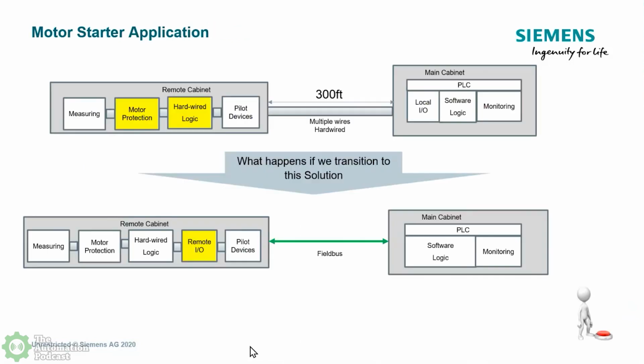So if we replace that with a field bus, and initially, back in the day for the seasoned individuals, we started working with RS 232, RS 485. For Siemens, the RS 485 communication protocol is Profibus. You may encounter Data Highway, Modbus RTU, and so forth. But the field bus started to help reduce all that wiring. It also gave some opportunity to move some things out into the remote cabinets too, because you started having bandwidth to where you could bring in multiple points of data with the same piece of wire and get statuses and so forth.